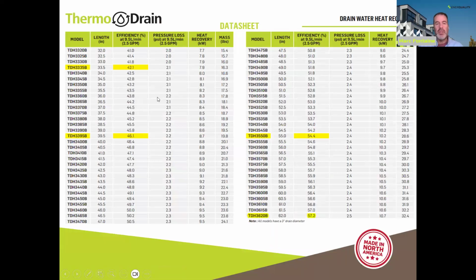One thing of note is that as the length of the unit becomes longer and longer, the efficiency of the unit also increases. On the really long units, there's a diminishing return, so the efficiency doesn't climb as fast anymore. So there's a good sweet spot, from the low 30-inch units to 40, 50-inch units, where you get the most bang for your buck in terms of efficiency versus length.